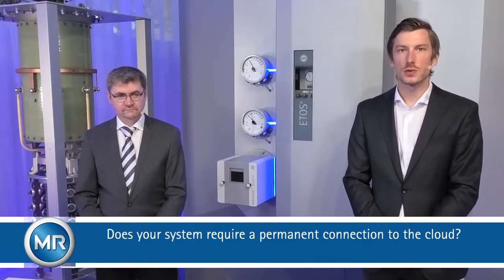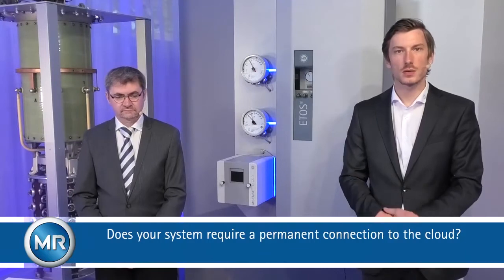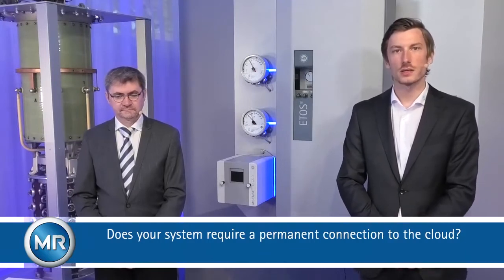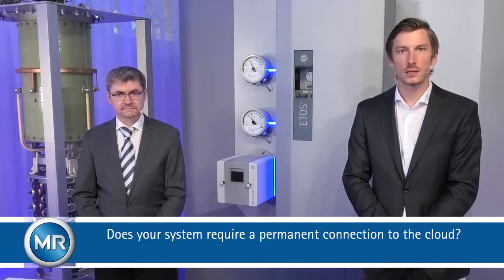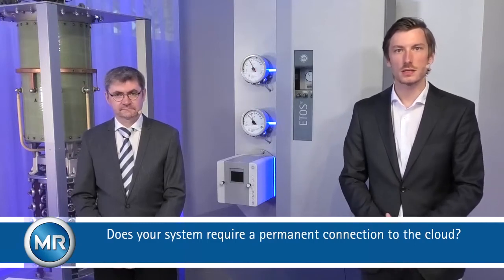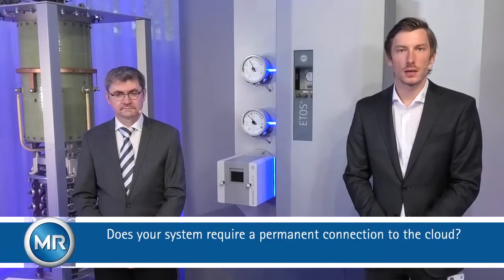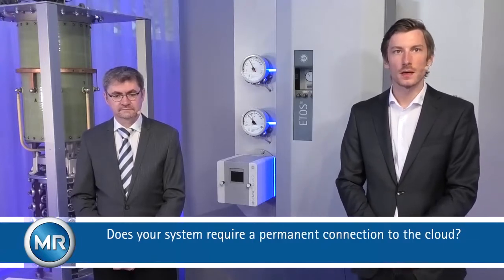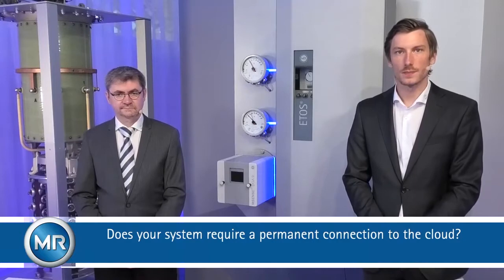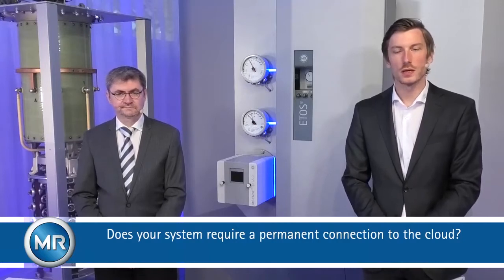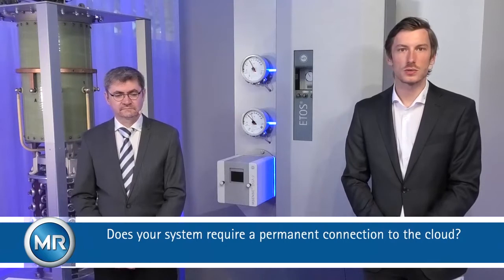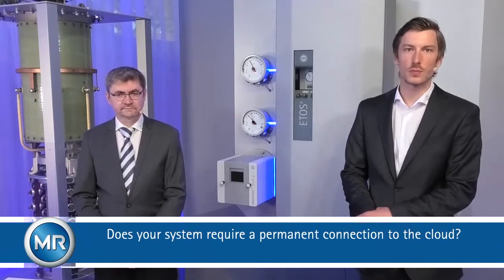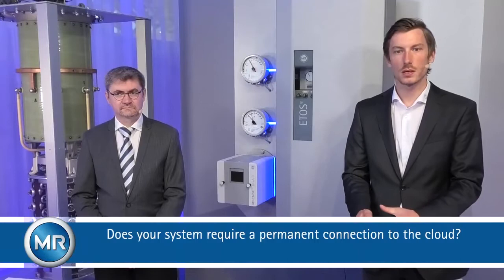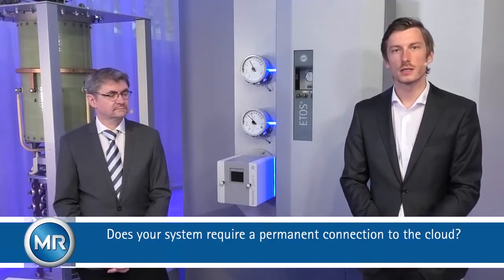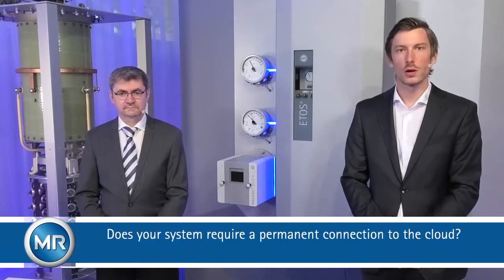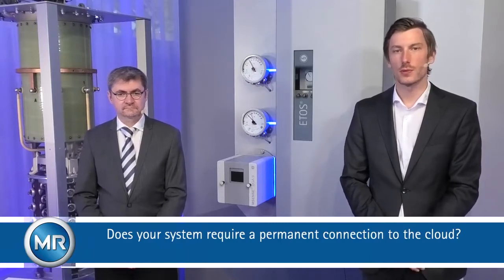So it can be to the SCADA system, for example. The standard way to connect intelligent control devices in the grid to a central system might be the SCADA system, or to an enterprise asset management system. So this could also be a way, and there you could use different ways to communicate, to get the data from ETOS to this system. In terms of the SCADA system, for example, 61850, 104, Modbus or DNP3.